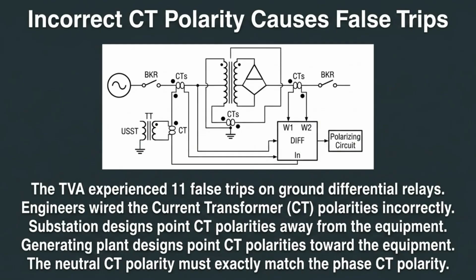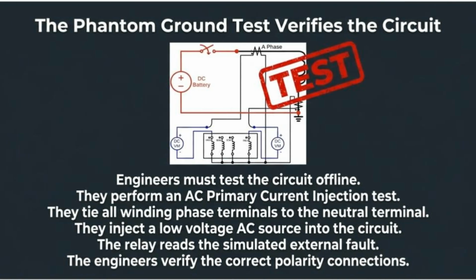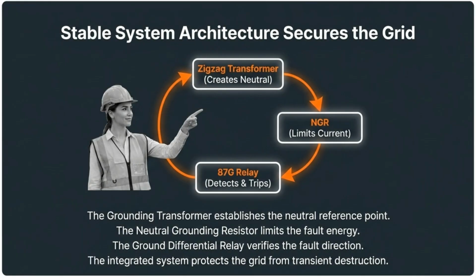Improper wiring of current transformers has caused numerous false trips. It is essential that the polarity of the neutral current transformer perfectly matches the phase current transformers. To verify these connections, engineers perform an offline phantom ground test. By injecting a low-voltage AC source into the circuit, they can simulate an external fault and confirm the relay settings are correct. By integrating the Zig-Zag transformer, the neutral grounding resistor, and the 87G relay, engineers create a stable system architecture that protects the grid from transient damage.